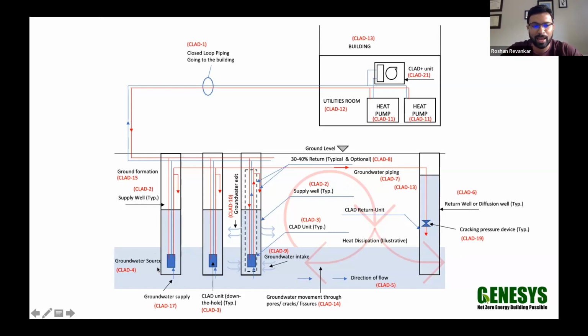All of the heat exchange happens inside the CLAD unit. We will look at what material it is made of and so on and so forth. But the CLAD unit can do both what we call active and passive heat transfer. Active heat transfer is essentially when the pump is running, but the material here is stainless steel. All of the heat exchanger is made of stainless steel. So it can also do passive heat transfer, which means that the pump does not need to be running all the time that the system is running.